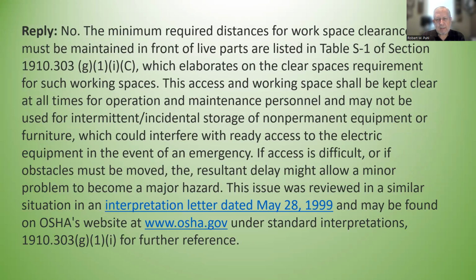No, the minimum required distance for workspace clearance must be maintained in front of live parts as listed in this table, which elaborates on the clear space requirements for such working spaces. This access and working space shall be kept clear at all times for operation and maintenance personnel and may not be used for intermittent incidental storage of non-permanent equipment or furniture, which could easily interfere with ready access to electric equipment in the event of an emergency.